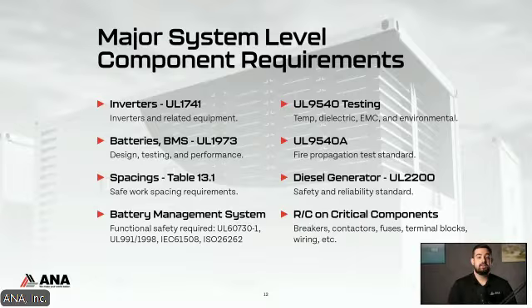Spacings. So this could be any kind of current carrying conductor, whether it's high or low voltage differences, or it could be your current carrying conductor and chassis or ground. You do need to meet table 13.1 spacings for these, so that table is going to be your best friend for this. Typically, if you have 1 inch between across the board, you should be okay. But again, this is going to be a case by case basis for your application or product.